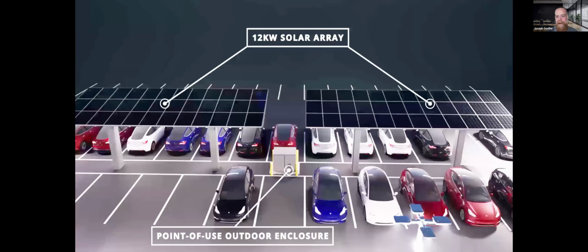We can take a better look at that on the next slide, right in the middle. This is a NEMA 3R outdoor power cabinet. It has enough battery storage to keep the lights and cameras running for up to 2 full nights if solar wasn't available. But like the indoor microgrid, this can also fall back on grid power, giving us resiliency for lighting and security.